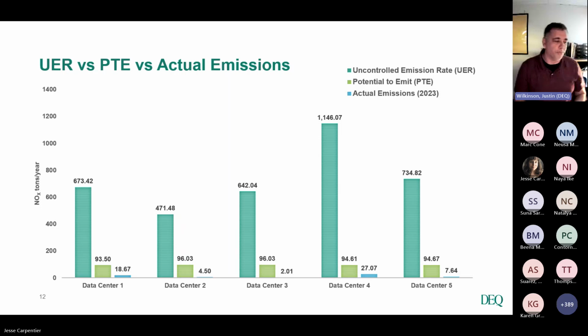Here on the graph we pulled an example from five data centers we have. The green, the highest bar on the left of each data center, is what we refer to as the uncontrolled emission rate. That's a calculation, and this is in NOx, our NOx emissions from these units, from these facilities, without any federally enforceable limitations, without controls.